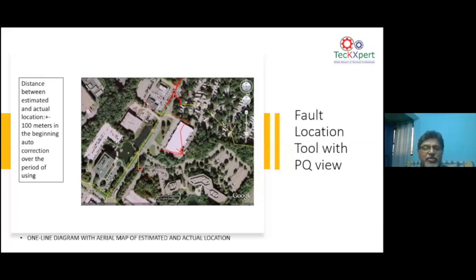Sometimes you can use this continuous monitoring to determine that there is an incipient fault, like an underground fault developing. Before the fault turns into a fire or a short circuit, by doing waveform signature analysis we can interpret that there is an underground incipient fault at this particular distance. By doing that, you can avoid a major short circuit in the underground cable. You can also use the right type of PQ analyzers, class A certified analyzers, so that they can do all types of power quality study, such as transients, sags, swells, harmonics and noise, rather than only concentrating on harmonics to find out the power quality problems.